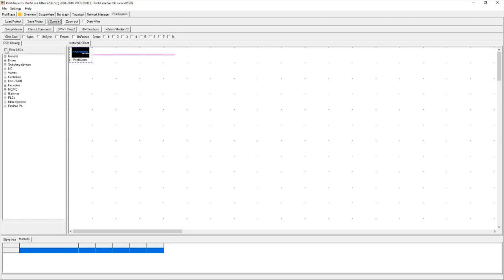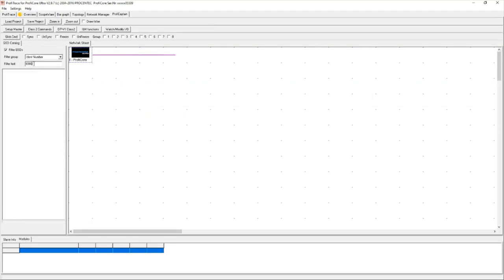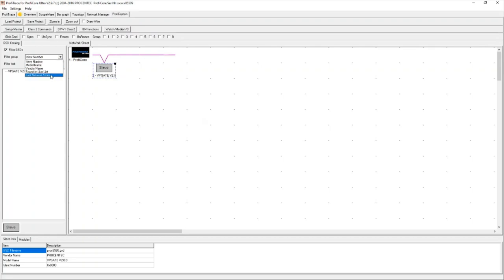To quickly add my devices, I can filter my GSD file by typing in that identity number — for example, 6980 for the VPGATE. An easier way is using the 'Last Network Scan' block, which automatically shows all devices scanned during the Class 2 network scan command. I've already added 6980; now I can add 6960, which is my IO module; then my Anybus Communicator; and finally my Revolution Pi at address 13. I'm simply dragging the GSD files listed on the left into the panel at the top so the master knows what devices it's connecting to.